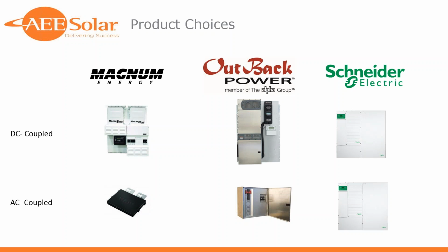Here's one from James. SolarEdge DC coupling uses high voltage, so doesn't low voltage wiring cost become an issue? The question is how we compare the DC runs of a SolarEdge system versus the DC runs of an Outback, Schneider or Magnum DC coupled system. I didn't touch on this too much, but for me that's apples and oranges.